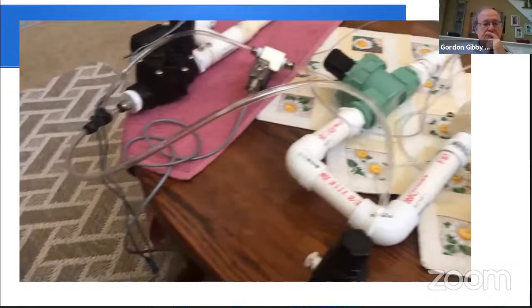In that T there are two components that are simply mechanical. One is an overpressure valve, the black part on the left, and the other is an anti-asphyxia valve, the white part on the right. And if a negative pressure shows up in the system, that will open and allow the patient to breathe. From there, the inspiratory system pushes air towards the patient through that tube and over to our fake patient.